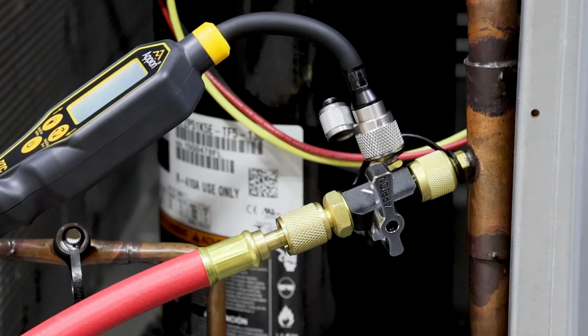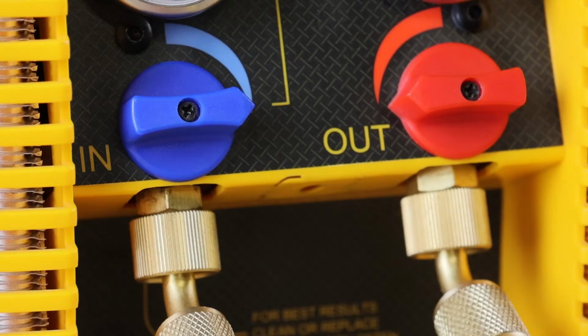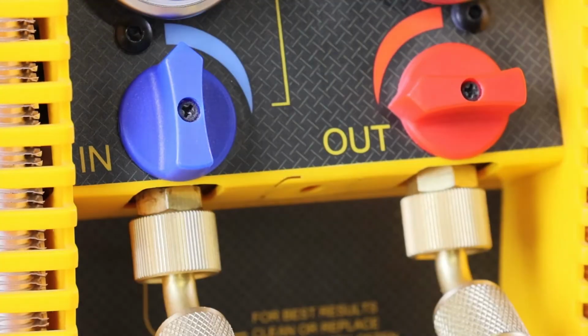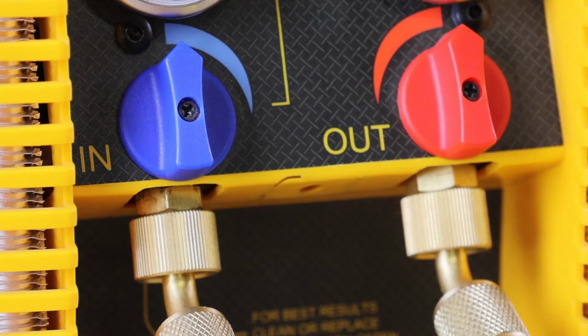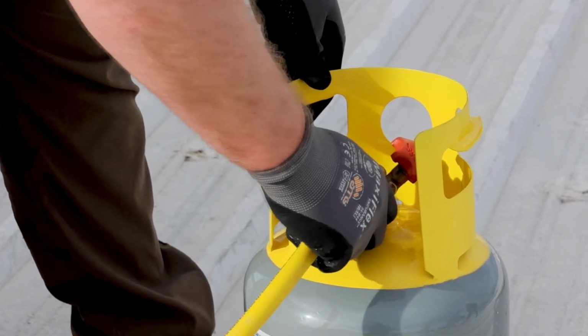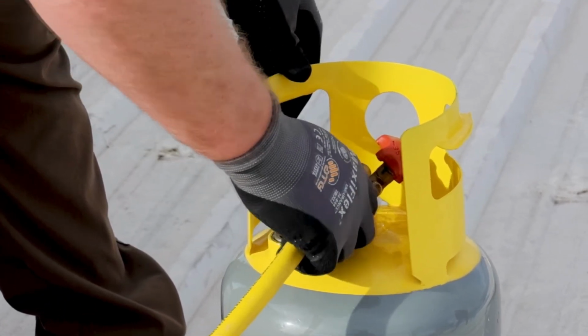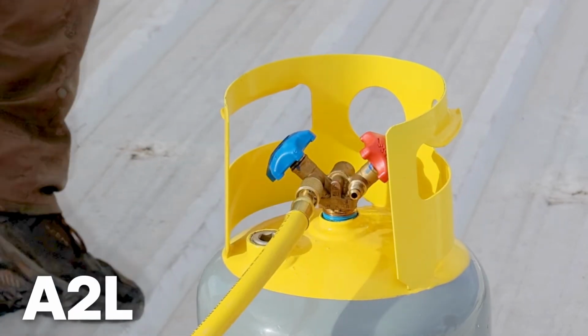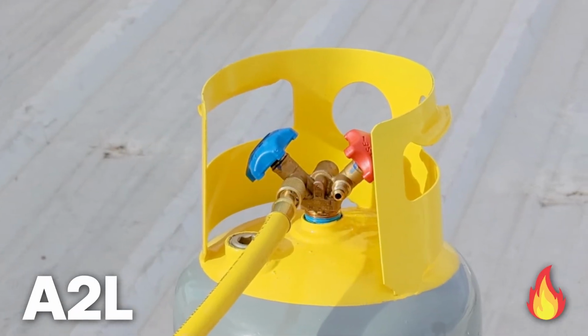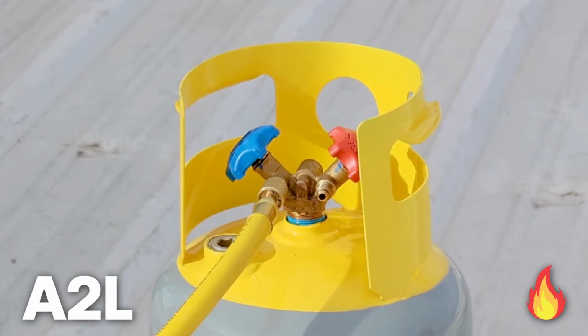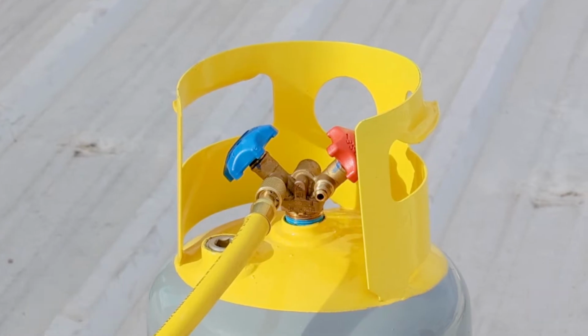Purging the entire recovery setup is essential to any recovery job and applies to all recovery methods. Purging the hoses and recovery machine prevents non-condensables, contaminants, such as moisture and oil from other refrigerants, and air from mixing with the recovered refrigerant. This is especially important when recovering A2L or mildly flammable refrigerants, since an air mixture can create an ignitable concentration. It also ensures that any refrigerant being reused or returned for recycling is in its purest state.